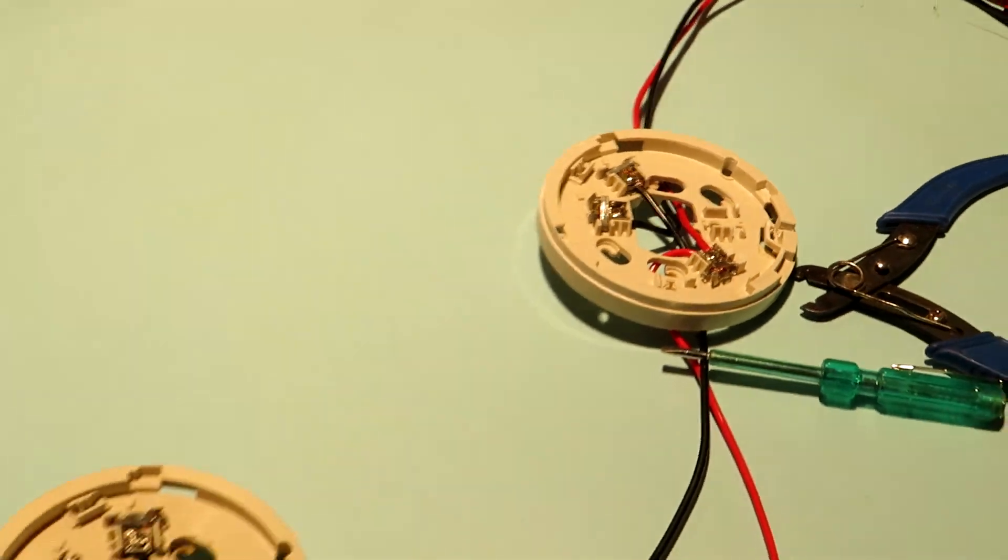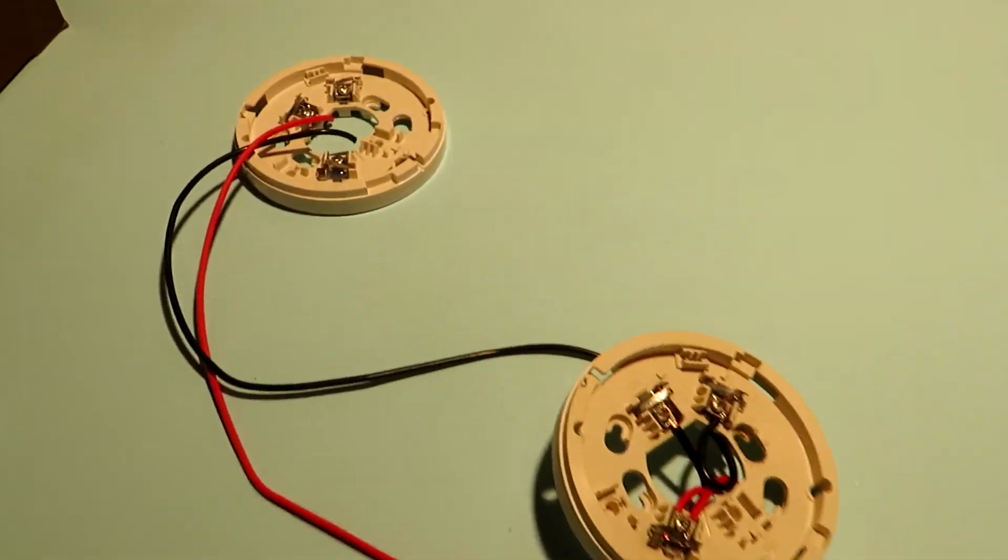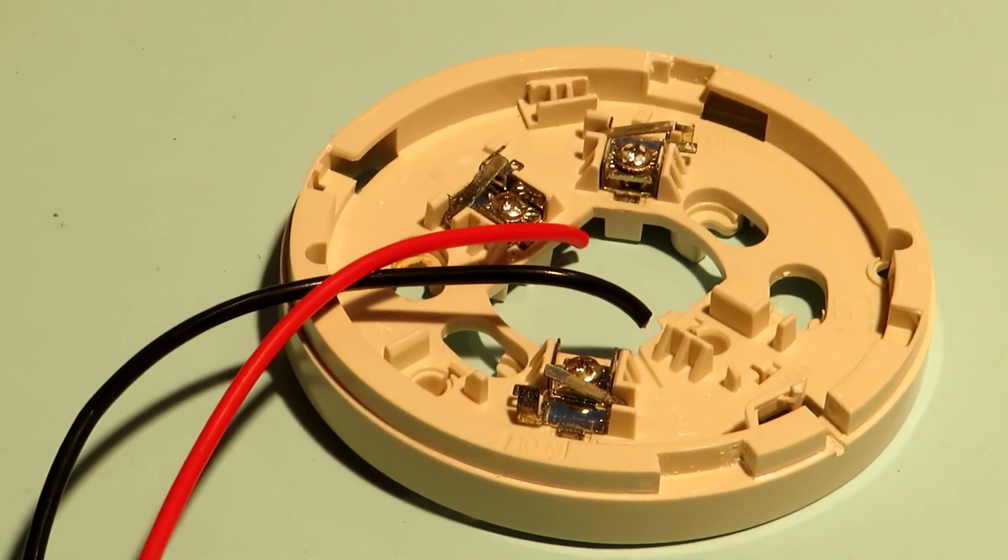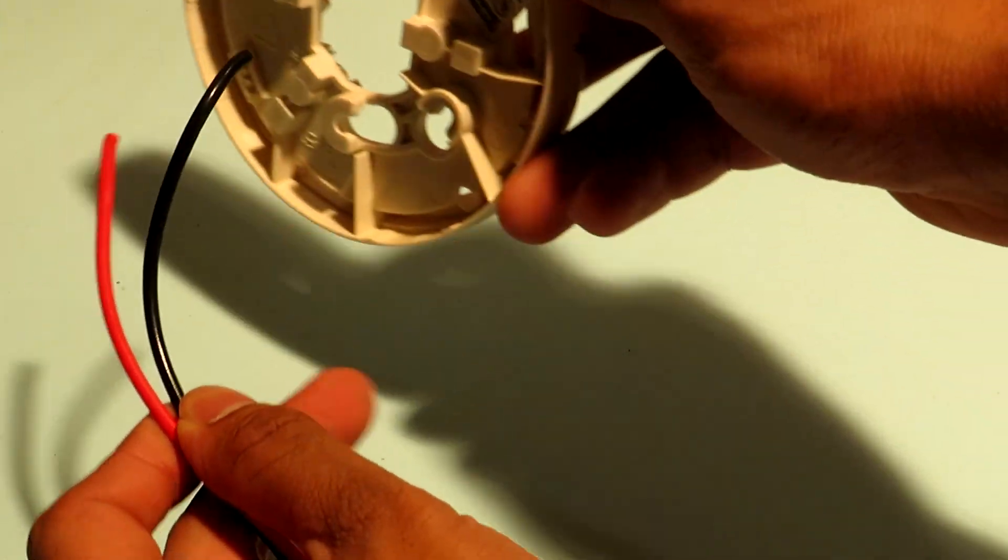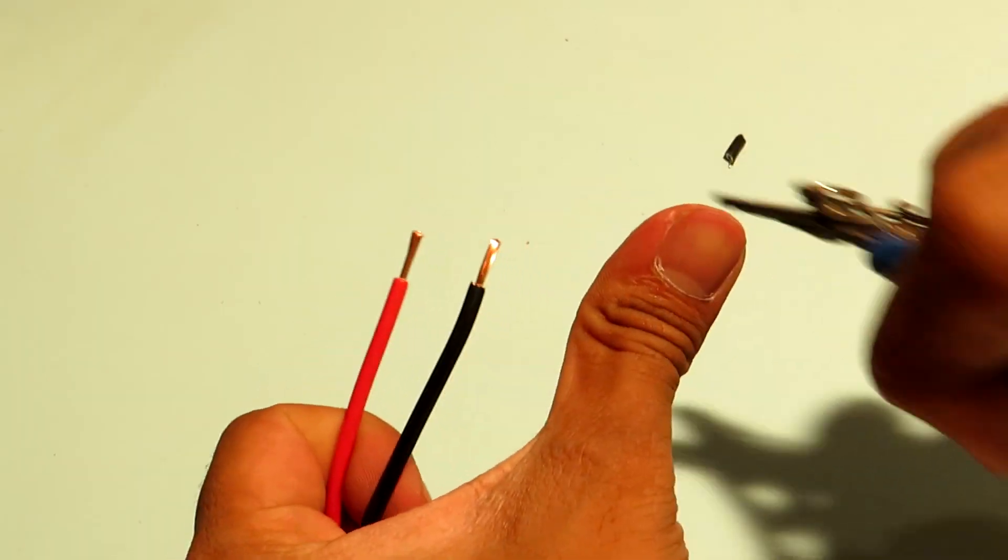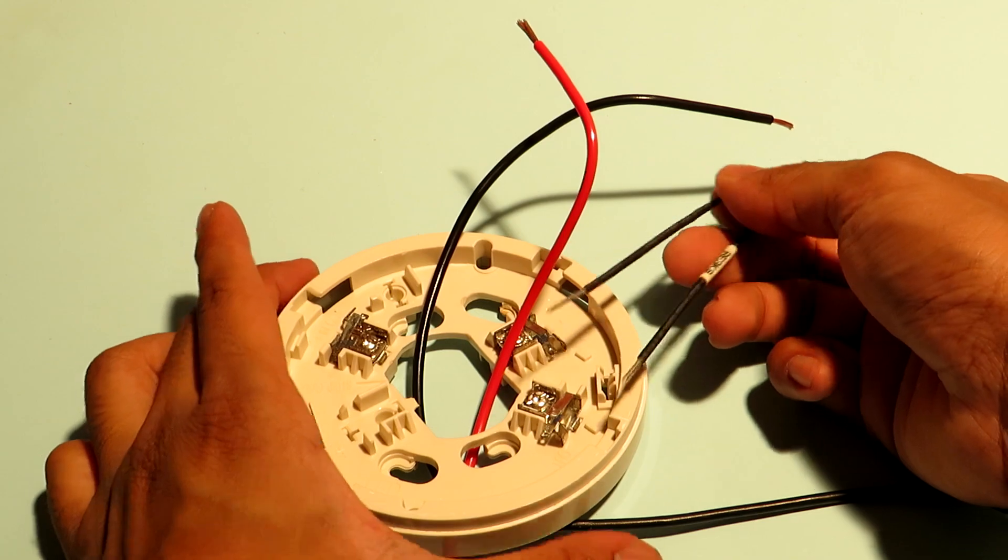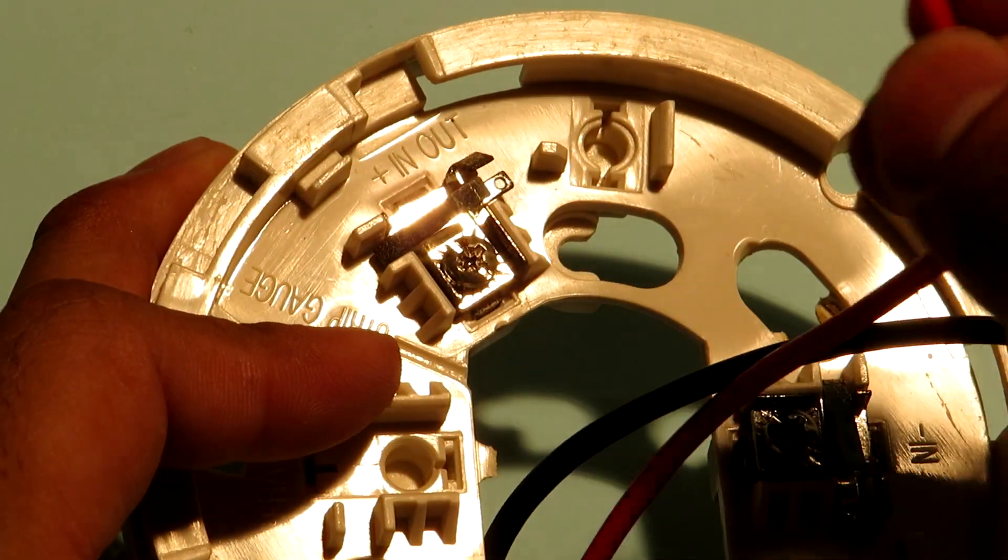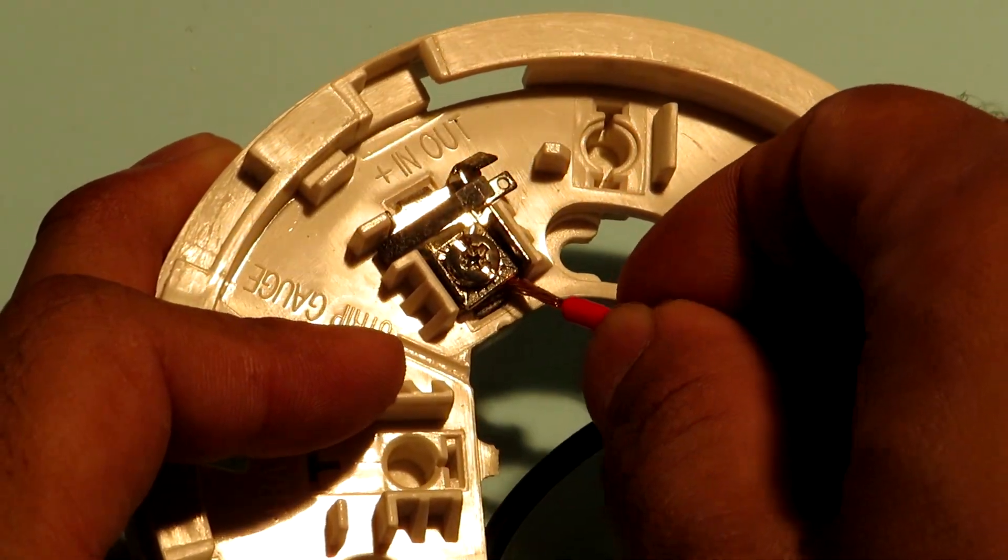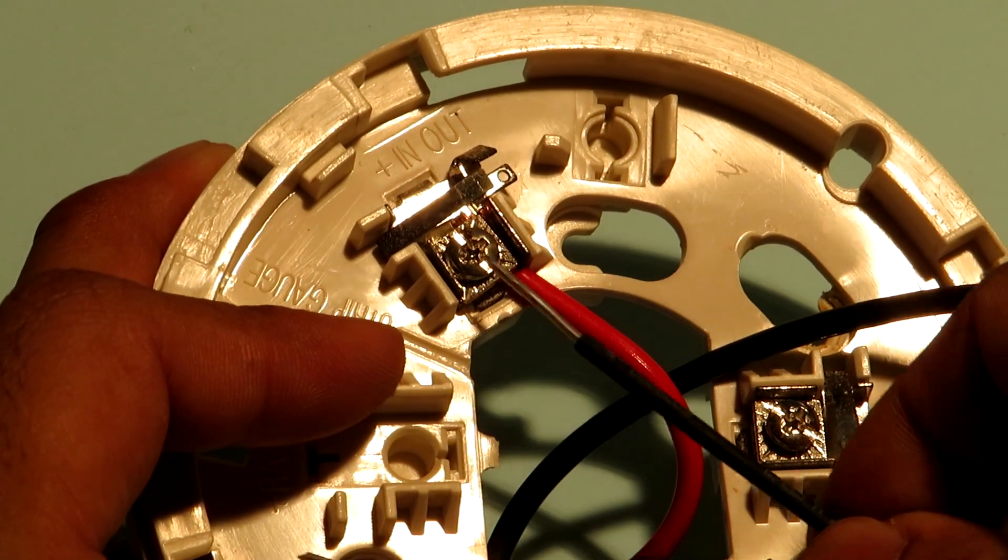So in this way two detectors have been connected in the line successfully and now we have our last detector to connect. So pass the wires through the base and skin them. Since this is the last detector in the loop our EOL resistor will come into picture. So as usual along with connecting the positive wire from the previous detector into the positive in out terminal we'll also have to connect one end of the EOL resistor to this terminal.